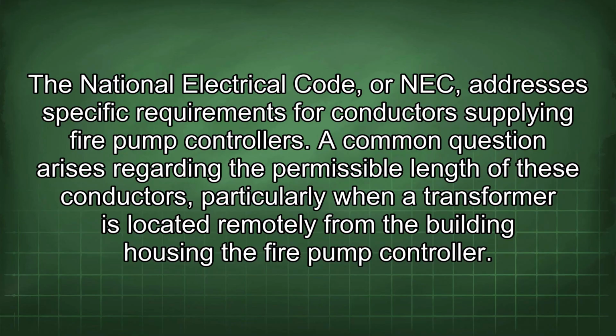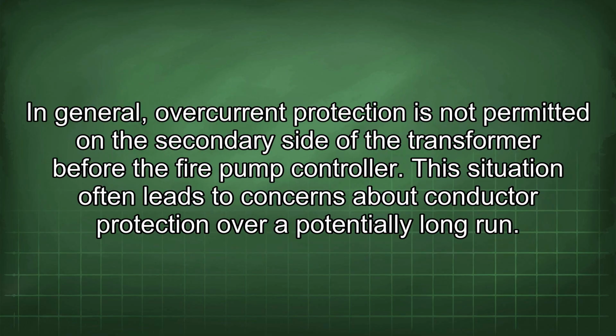The National Electrical Code, or NEC, addresses specific requirements for conductors supplying fire pump controllers. A common question arises regarding the permissible length of these conductors, particularly when a transformer is located remotely from the building housing the fire pump controller. In general, overcurrent protection is not permitted on the secondary side of the transformer before the fire pump controller. This situation often leads to concerns about conductor protection over a potentially long run.